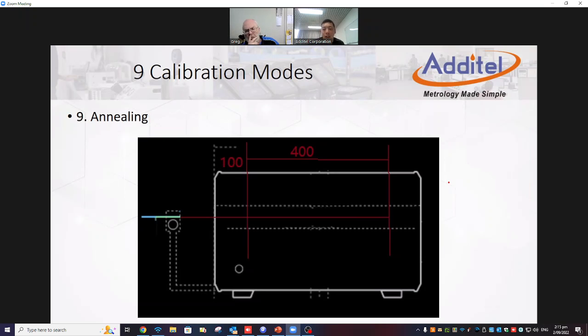This is annealing. So when do the customers need to do the annealing? Normally, it depends on the using frequency of their probe. But normally, we do recommend to do the annealing once a year. Because annealing is pretty simple with this solution, they just drop the probe and get high temperature, and that's it. So normally it's just once a year.